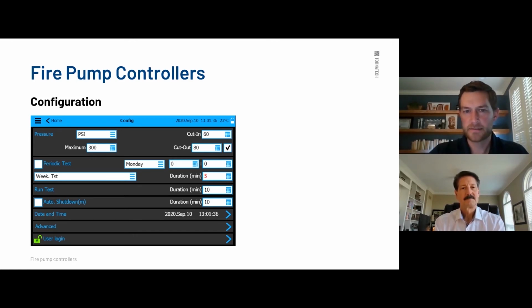The run test, that's going to be how long the test is actually being run for. That's actually controlling how long that front button operates. So if you press that, it'll run for 10 minutes. Then automatic shutdown. So automatic shutdown, this is where you would come again to enable that. It's the same process as all this other stuff. You just need to click that checkbox and it'll be set up for automatic shutdown.